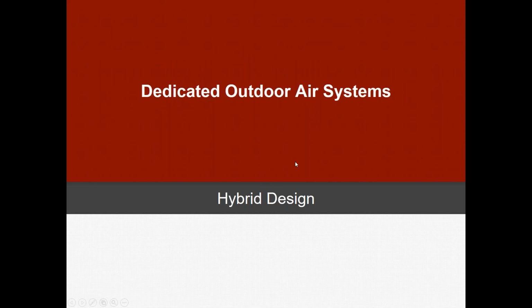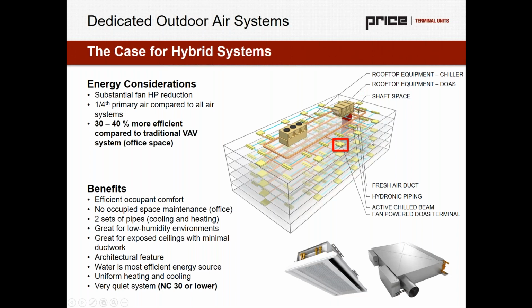So this kind of leads us to this idea of hybrid design in particular. And we can see the schematic here with both those beams and the fan-powered terminal units together in the configuration that I maybe think would be optimal, where we tend to have the larger turn down, more easy to integrate reheat fan-powered terminal units on the exterior zones, and then potentially some beams on interior zones.